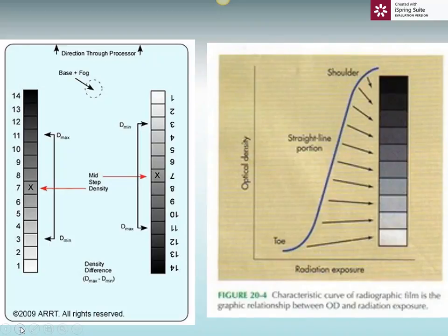Here's an example of a couple more here. For example, what you are looking at is another sensitometry strip, and what you do is you measure these various points and you plot the values. Now, I'll show you this in lab when we have a moment as to how these densitometers measure things. Suffice it to say, it is based on a logarithm, so that it doubles essentially in density every 0.3. And that's very similar to Kodak imaging and things like that.